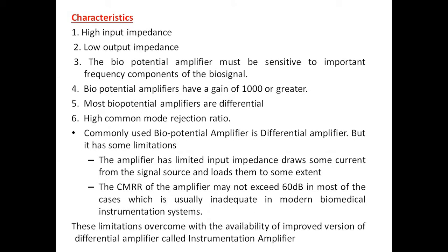What are the various characteristics of biopotential amplifiers? High input impedance and low output impedance. The biopotential amplifier must be sensitive to important frequency components of biosignals. Biopotential amplifiers have high gain of 1000 or greater. Most biopotential amplifiers are differential in nature. High common mode rejection ratio. These are the six important characteristics for a biopotential amplifier.